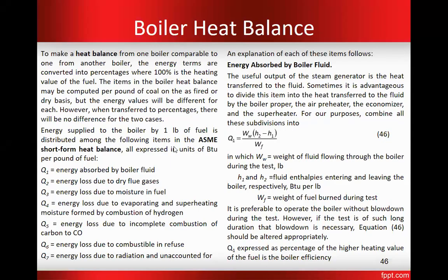Boiler heat balance. To make a heat balance from one boiler comparable to one from another boiler, the energy terms are converted into percentages where 100% is the heating value of the fuel. The items in the boiler heat balance may be computed per pound of coal on the as-fired or dry basis, but the energy values will be different for each. However, when transferred to percentage, there will be no differences for the two cases.